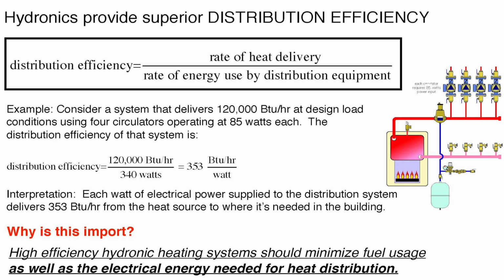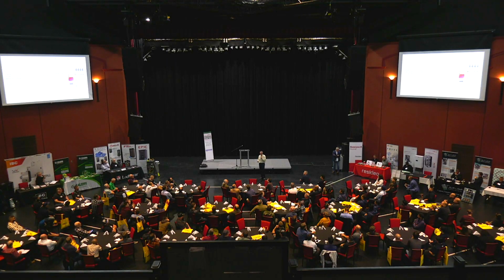And what does it mean? Well, the way you can interpret it, for each watt that you supply the distribution system, it is delivering 353 BTUs per hour where they need to go in the building. Now, is it good, or is that average, or is it poor? What do you think? I don't know. You don't have anything to compare it to, right? You need some kind of a number to compare it to.